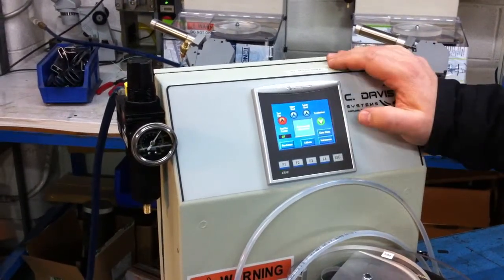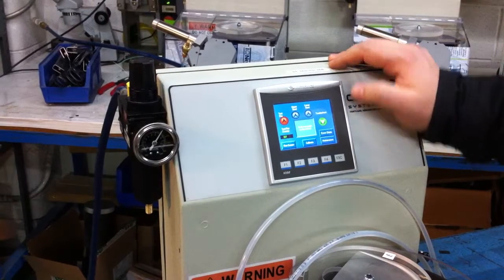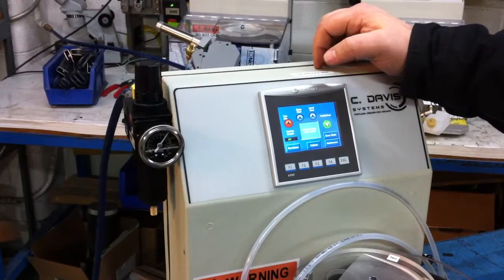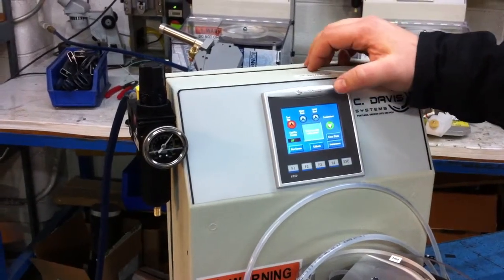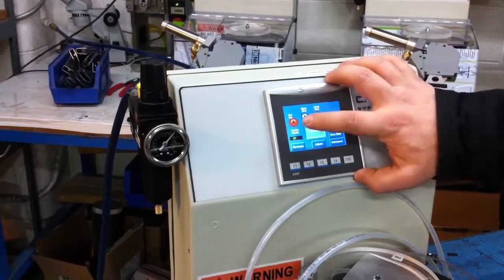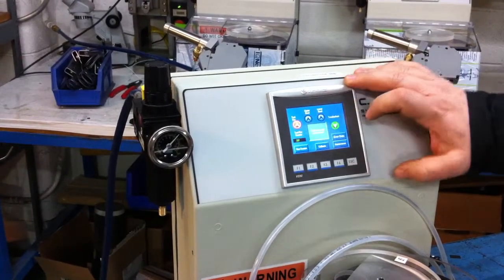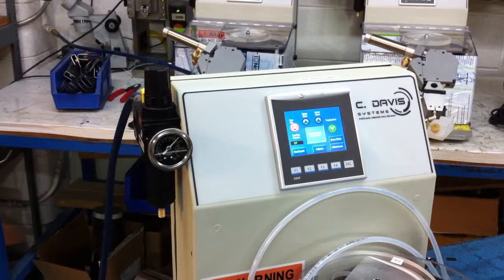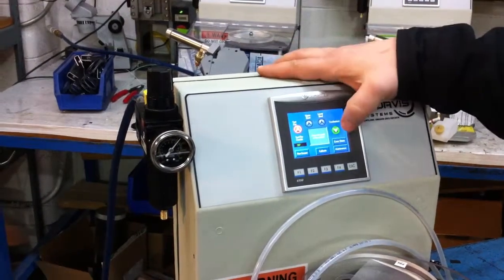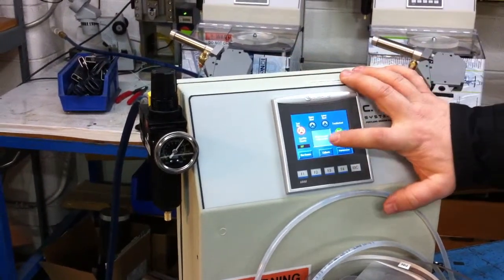You have maintenance 2. Maintenance 2 allows you to do a little bit of troubleshooting. From here you can test fire. You press test fire, and then you can disconnect your feed tube and fire the terminals in your hand just by pressing the foot pedal, which is indicated on the screen.